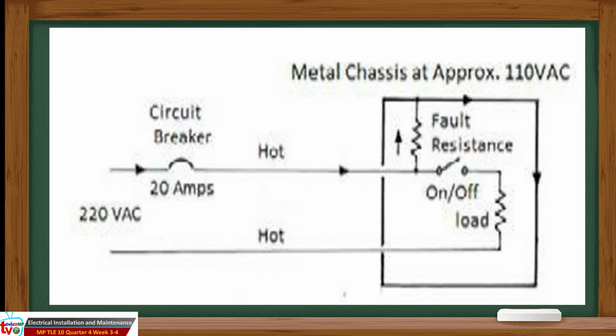shows the schematic diagram of an appliance without an equipment grounding conductor connected to the metal chassis. The appliance is sitting on a wood table and therefore isolated from earth ground. The appliance is turned off, but a wire insulation fault has occurred before the switch. The chassis of the appliance is at an electrical potential of 110 volts with respect to ground. Since it is switched off and there is no path for fault current flow, no current flows in this circuit.